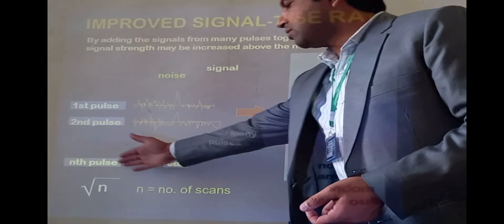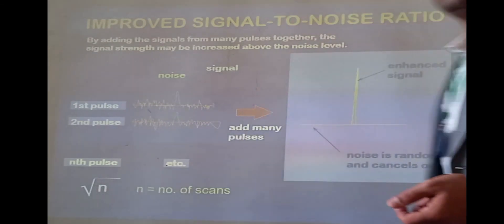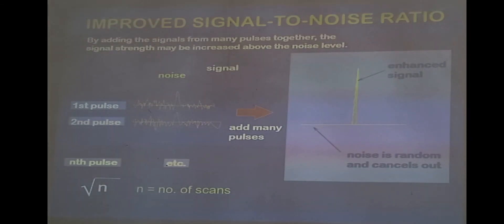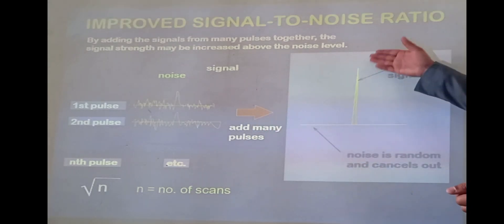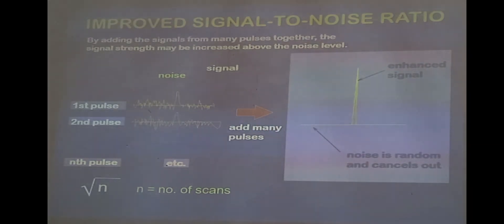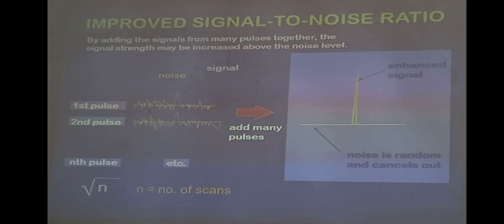So for any number of scans n, the signal-to-noise ratio is equal to the square root of n. After many pulses and many scans, you will have a very clear signal with minimum noise levels. This is how you can increase the signal-to-noise ratio and obtain a better, cleaner spectrum.